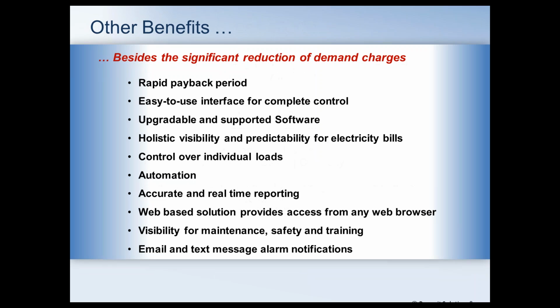And finally, Dick has talked a lot about the experience he's had utilizing Sparrow Demand Manager to reduce his peak demand charges and to participate in demand response. Some of the other benefits of our technology: the Sparrow system provides real-time visibility to the plant-wide energy consumption. This can be used for maintenance, seeing if something's going wrong with a furnace or a power supply, and also for safety, to make sure that pieces of equipment are consuming the correct amount of electricity.